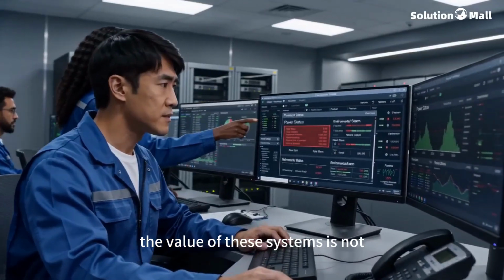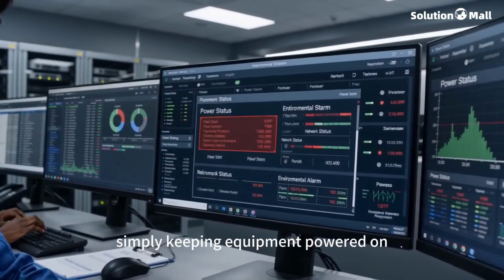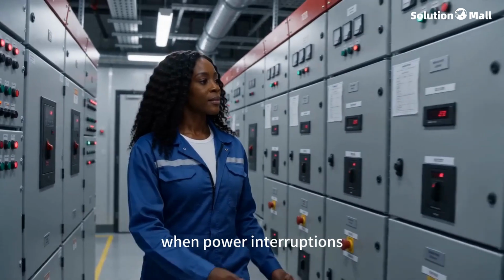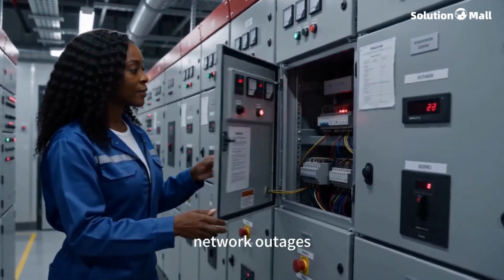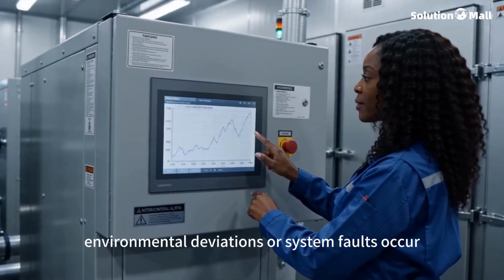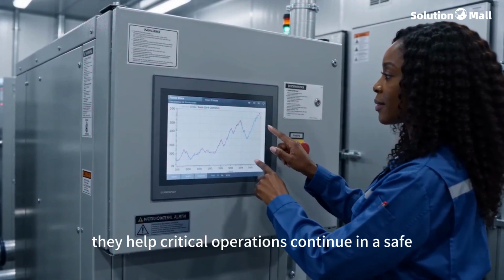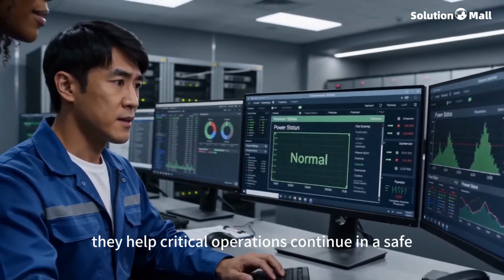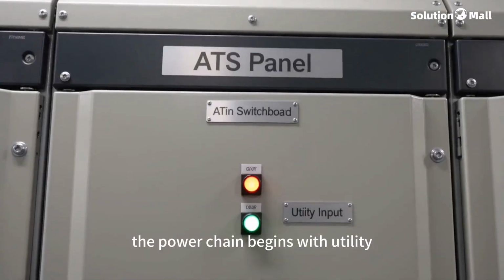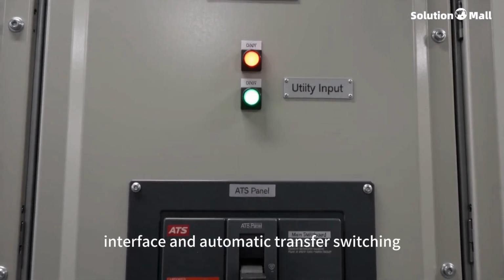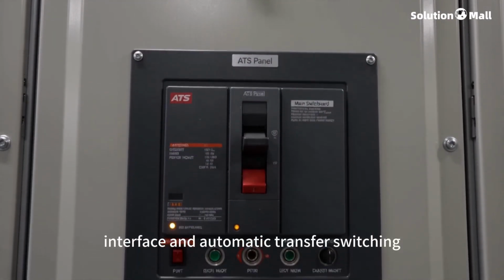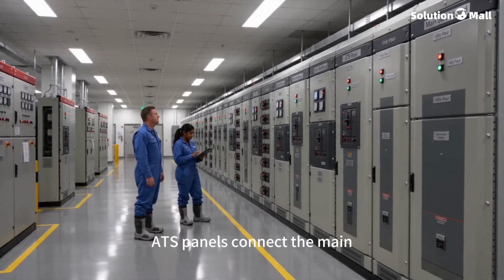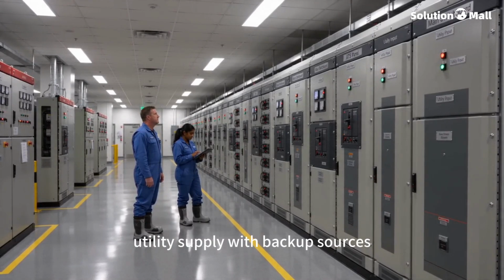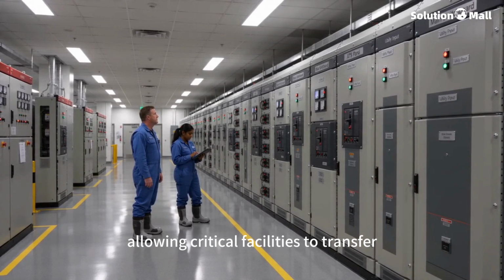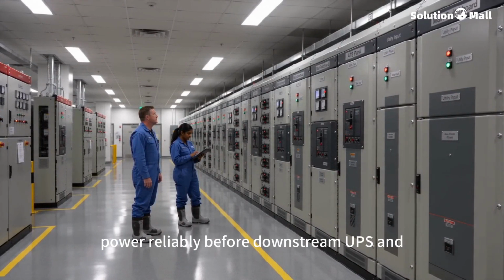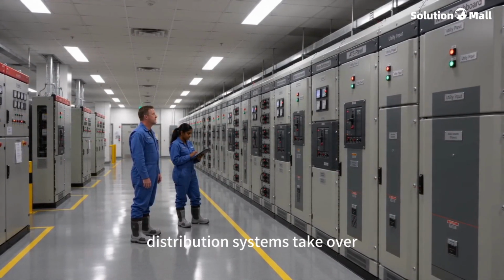The value of these systems is not simply keeping equipment powered on. When power interruptions, temperature drift, network outages, environmental deviations, or system faults occur, they help critical operations continue in a safe, stable, and controlled manner. The power chain begins with utility interface and automatic transfer switching. ATS panels connect the main utility supply with backup sources, allowing critical facilities to transfer power reliably before downstream UPS and distribution systems take over.